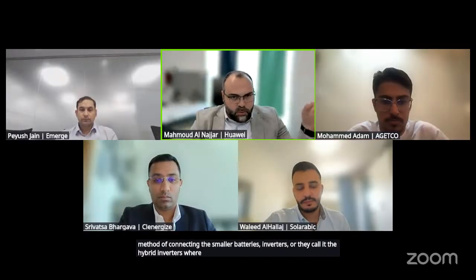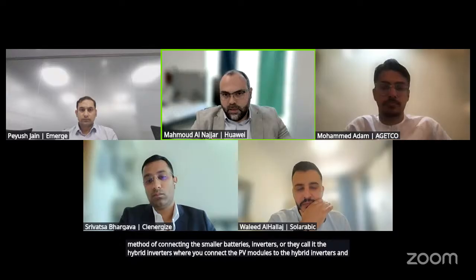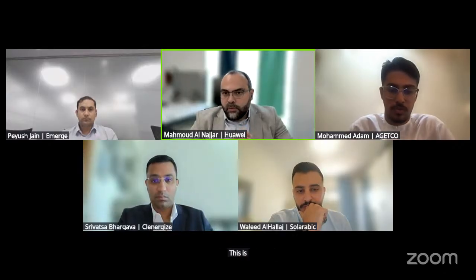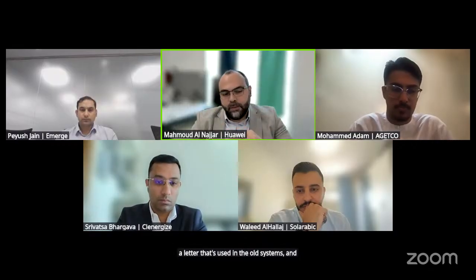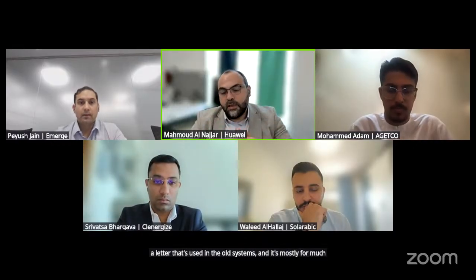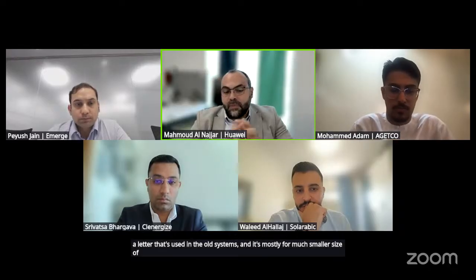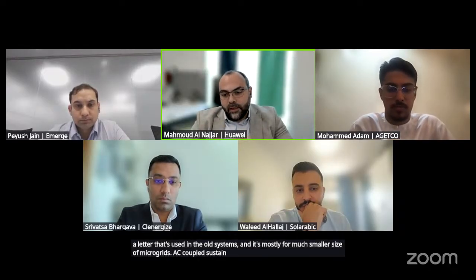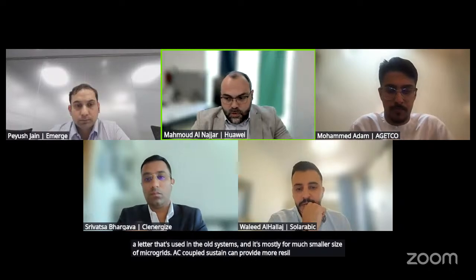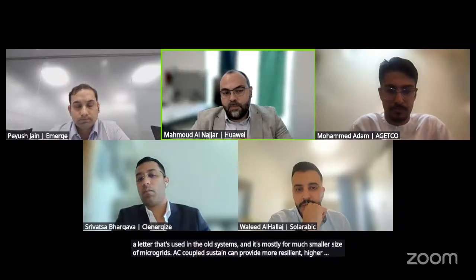Typically, DC coupled systems are the old method of connecting the smaller batteries and inverters, or what they call hybrid inverters, where you connect the PV modules to the hybrid inverters and connect the batteries to the hybrid inverter. Then you have an output. This is used in the old systems, and it's mostly for much smaller microgrids. An AC coupled system can provide more resilience, higher efficiency, and can be scalable to much larger capacities.